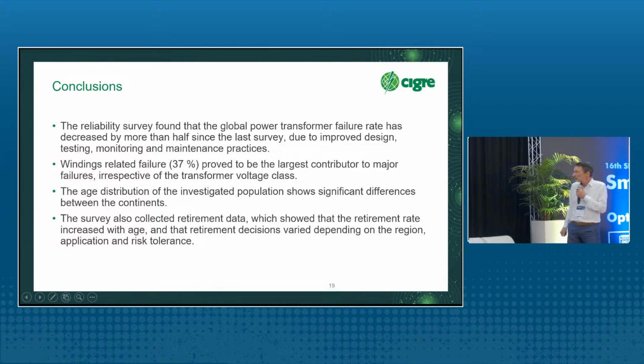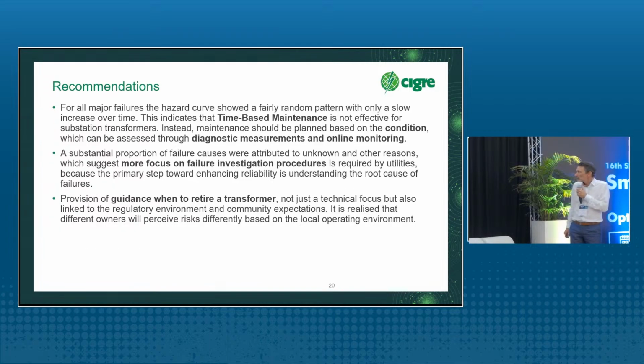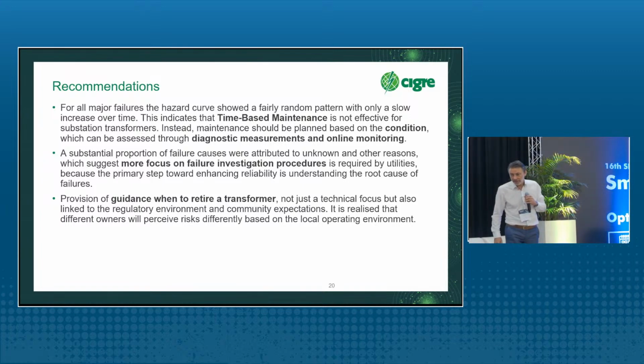The age distribution of the investigated population shows significant difference between the continents. And so we recommend not time-based maintenance. We could recommend condition-based maintenance, so diagnostic measurements and online monitoring. Also, utilities should more focus on failure investigation. And third, it is also necessary to give the regulators, let's say, a better understanding when transformers should be retired. This was, let's say, the first part of my presentation.